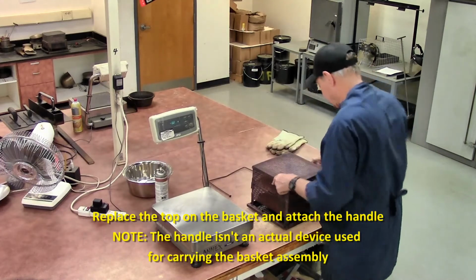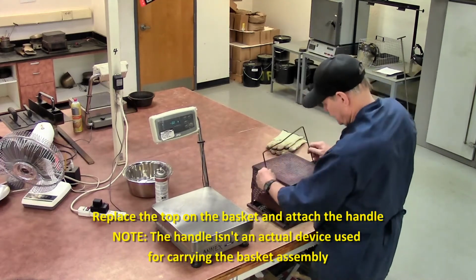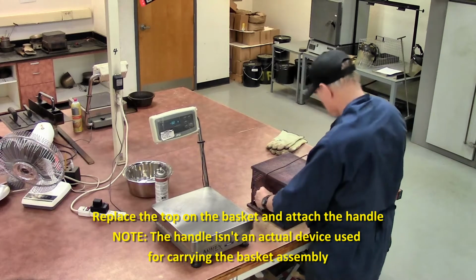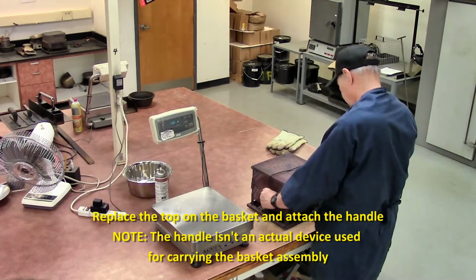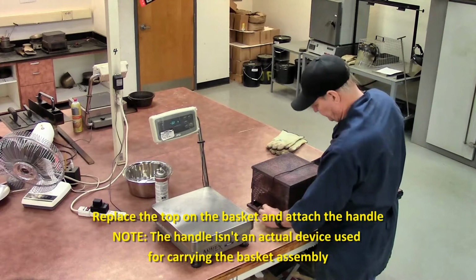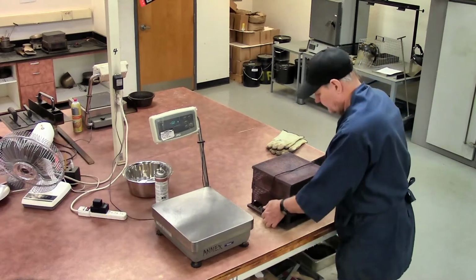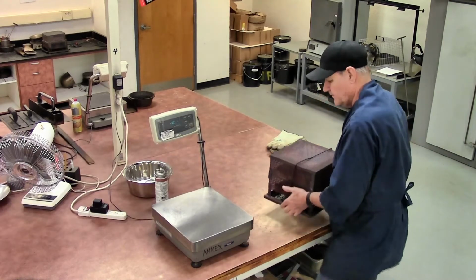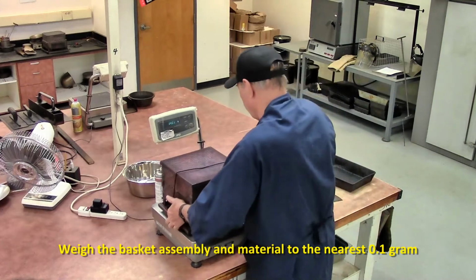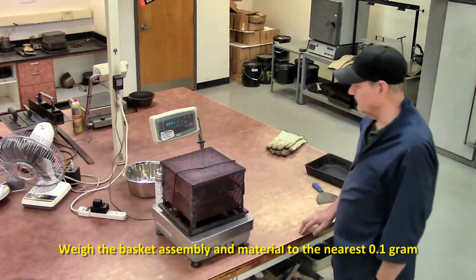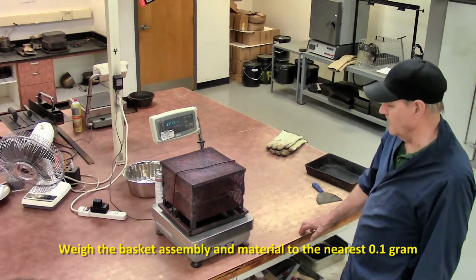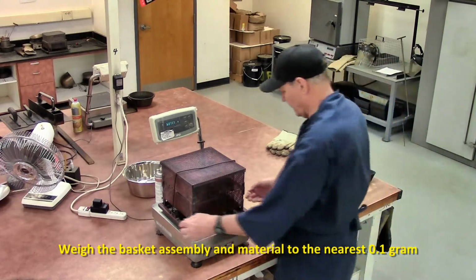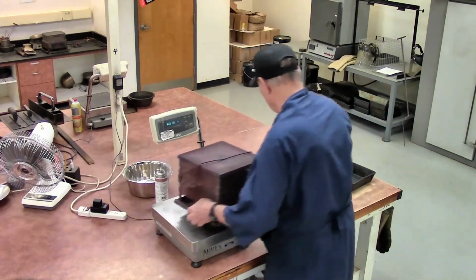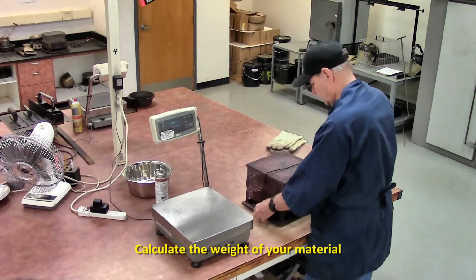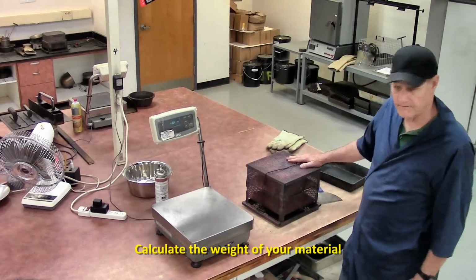Top on the baskets and the handle here. We call it the handle, but make sure you do not lift it by the handle. Okay, so now I need to weigh the basket assembly again with the material in it. Weigh that to the nearest 0.1 gram. I can subtract out the tare weight of the basket, the empty weight, and that will give me the weight of my sample. This goes into the furnace.